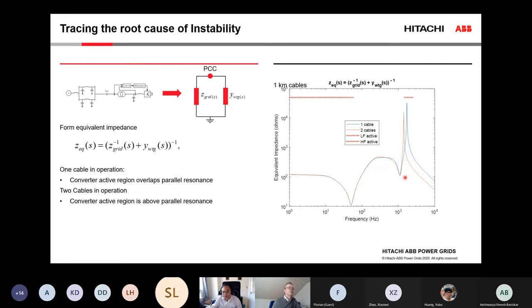One here is with one cable in operation, where if you remember from the previous slide, we were unstable. And in the other case, we have two cables in operation. It's a little bit tricky to see here, but you see that this resonance is clearly in the area where we have active behavior of the converter system. So it basically means that the converter system is seeing these variations at the resonance frequency, and it's constantly feeding more energy into it. So it's contributing to this instability. Whereas with the impedance calculated for the case with two cables, we are not in the active region. This amplification does not occur.